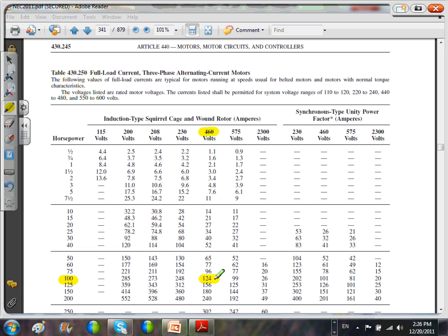If I want to run this motor at 208, you go over here. Look why it's important to run at a higher voltage. Look at the amps. Can you see the difference? The same amount of work. If you lower the voltage, it gives you a huge amount of amps. Who cares? I always say, who cares? Look at the conductor that you need to carry these amps compared to this. So bigger conductors, bigger conduits. Every time I say that, people say, well, Chad, job security, they need us. You know, other than job security, it's not an efficient system.